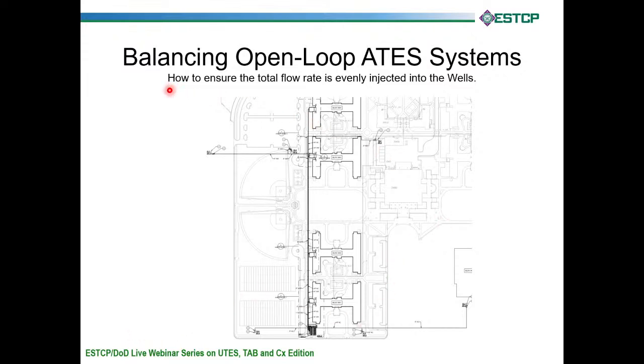So we've talked a little bit about balancing closed loop systems. Let's talk about how you balance an open loop system, such as an ATES system, Aquifer Thermal Energy Storage. How do we ensure that the total flow rate of the system is evenly injected into the wells? Just as a refresher from our last webinars, this is an ATES system in Pensacola, and we're currently designing this. We have 3 cold wells here, and here are 4 buildings. So this is on a pretty large scale. 4 big barracks buildings, 3 cold wells here, 3 warm wells over here.